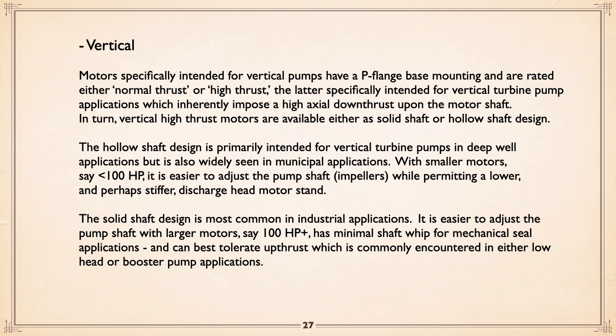The solid shaft design is most common in industrial applications. And again, in the bigger motors, it's easier to adjust the pump shaft because the adjustment is under the motor, not on top, and it has less shaft whip for the mechanical seal, because it is a solid shaft. And you'll see how the hollow shaft is done. Hollow shafts can get a bit of whip in them, which mechanical seals don't like. So solid shaft is better with mechanical seals.